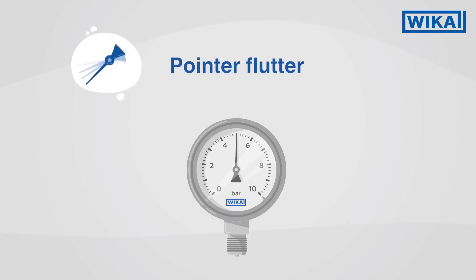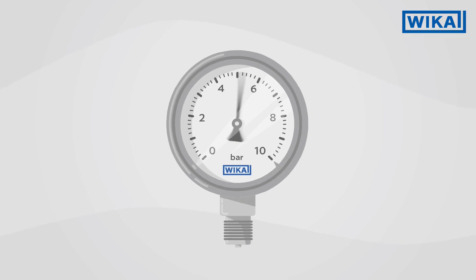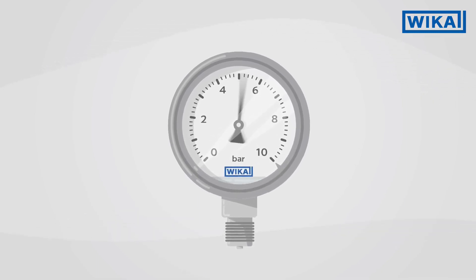Pointer flutter. This phenomenon can occur when vibration or pulsations act on the pressure gauge. The filling of the pressure gauge inhibits pointer flutter and ensures a correct pressure reading.